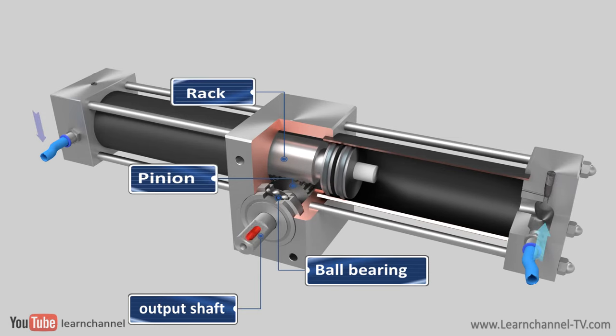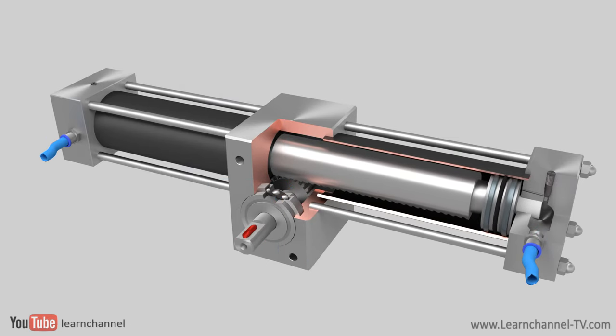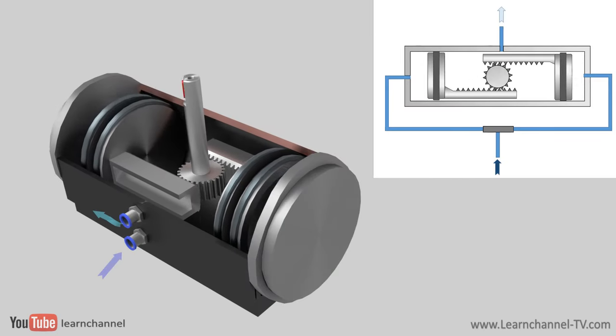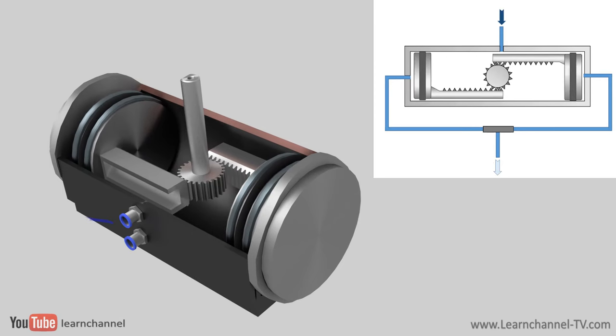Compressed air on the left-hand chamber produces clockwise rotation. Rack and pinion rotary cylinders offer a wide range of torque and rotation. They are mechanically stable and provide radial load support.